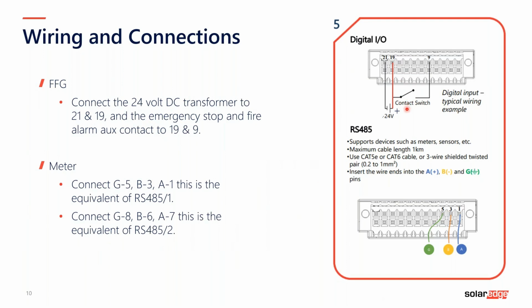One point to note is that you can change this from normally open to normally closed. So you have to physically set whether you have normally open or normally closed. You must check that before, when you're doing the commissioning. But this is the physical wiring. So 21 is negative, 19 is plus, and number 9 is the control wire or return.